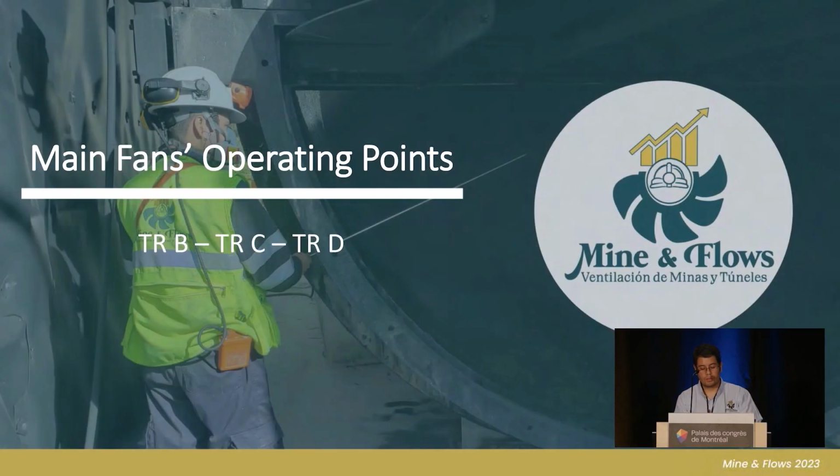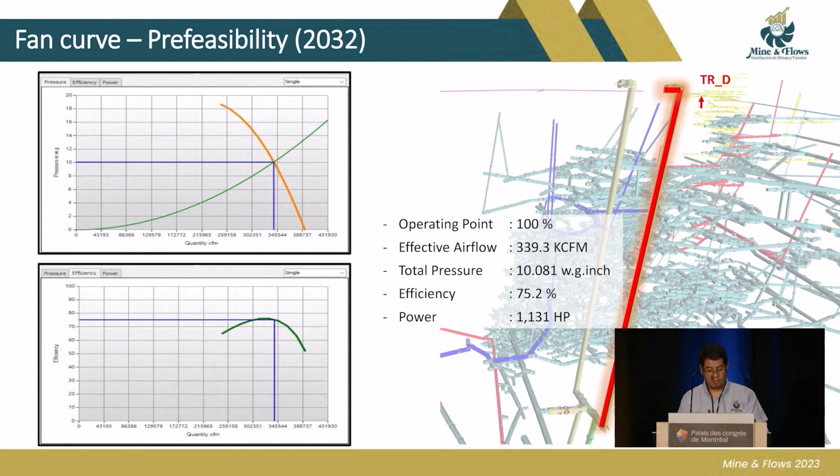The other point of discussion was the correct setup of the mine fans. From the identified opportunities for improvement and the tools provided by Ventsim, we could verify that an adequate reconfiguration of the ventilation circuit would result in typical operating points, similar to other mines in Peru, preventing overestimated CAPEX and OPEX related costs in the mine ventilation system.